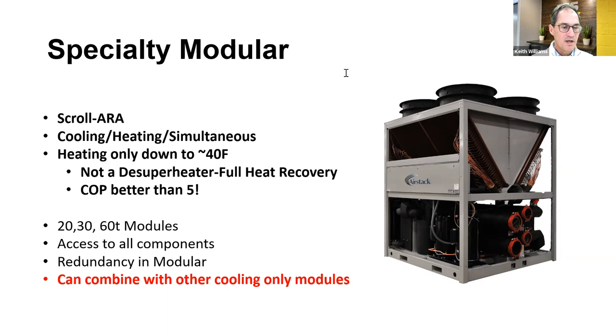Next question. Can we use these chillers in a very low temp brine application, say like a 10 to 14 degree type application? Absolutely. Yeah, we do a lot of ice skating rinks. Ice skating rinks typically are about 15 to 22 degrees. Those we've done all the time, air-cooled and water-cooled ice-making chillers. Our bottom end temperature is about 5 or 6 degrees.